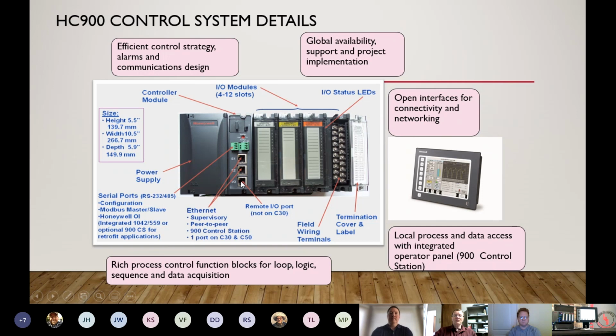The last port here is I/O. This is for additional I/O. So you can have additional HC900 racks hooked up to the single CPU, and the system can actually grow with the process. So if you get into an application, let's say for example you have one boiler that you want to control this with, but later on the plant adds additional boilers or additional control loops that they want to control and monitor. As your I/O grows, you can hook on additional racks through this port and have those out in the field.